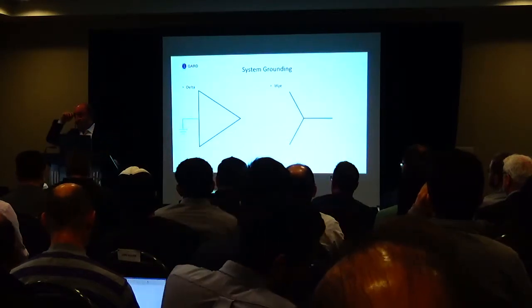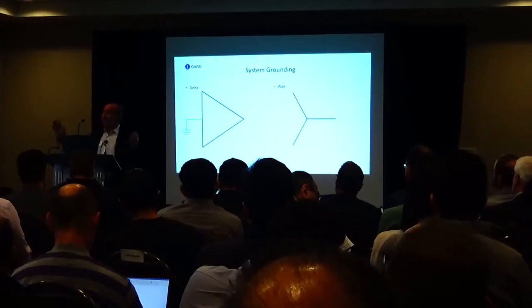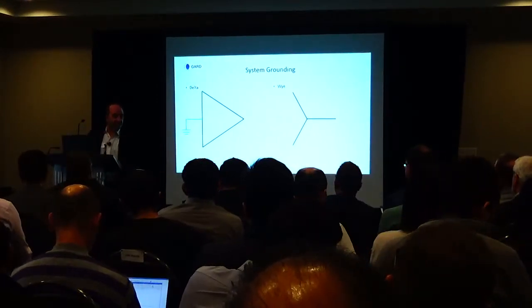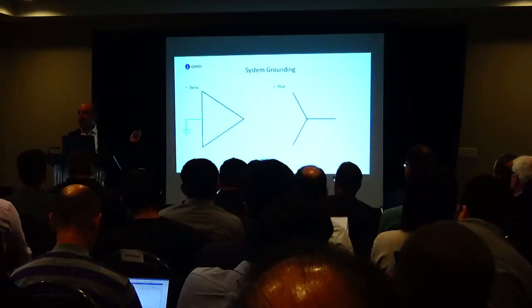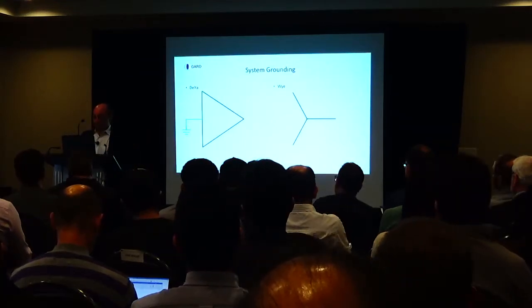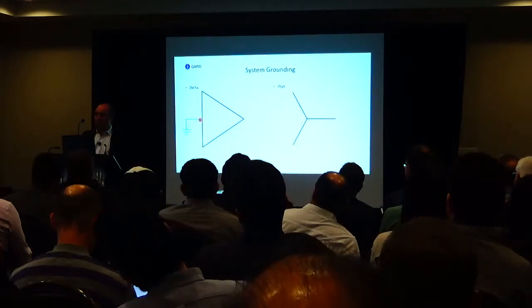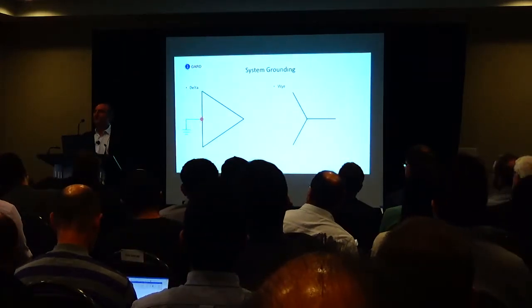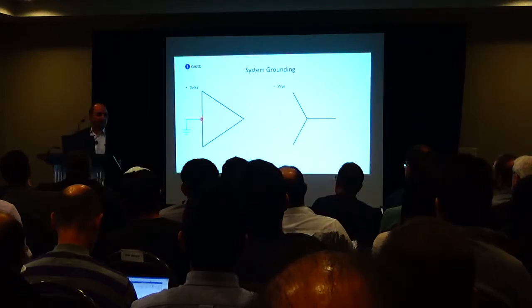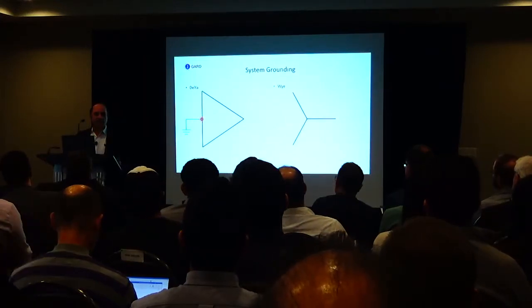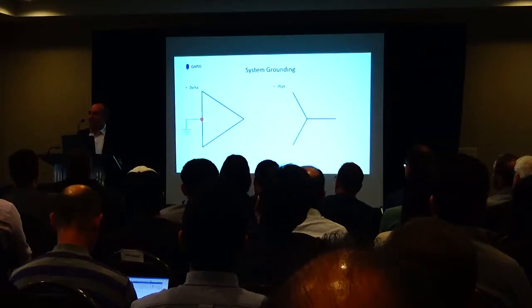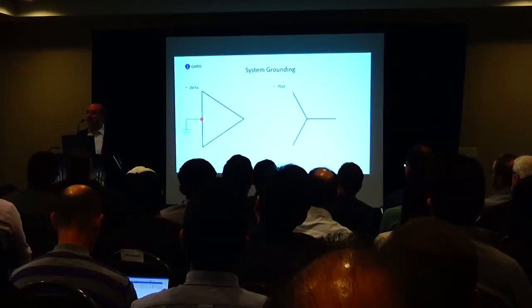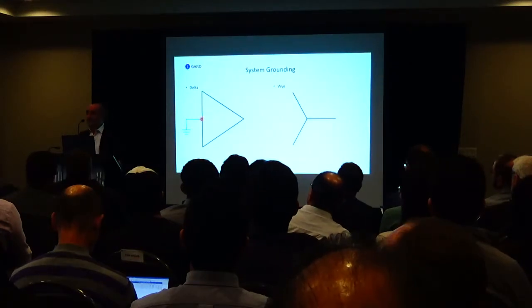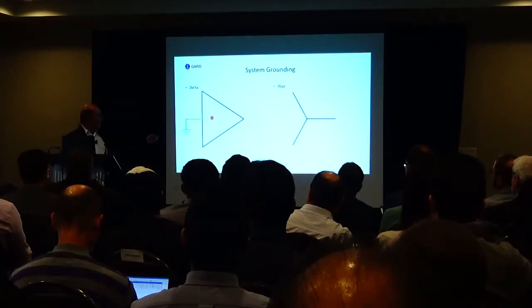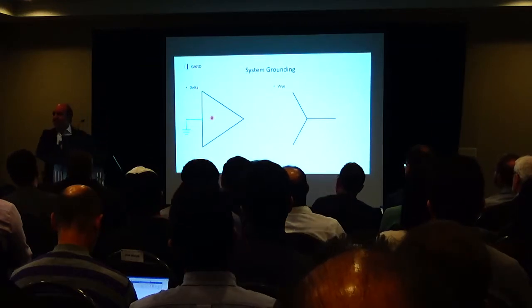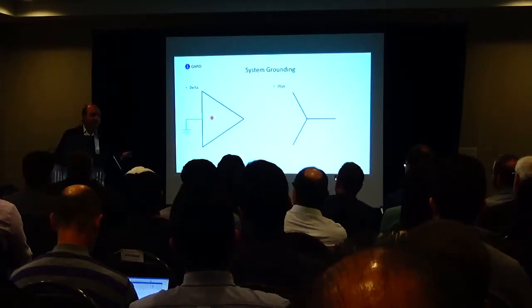So this is the one that you're used to. So you measure on, let's say for example, a 240 volt system. 240 volts phase to phase, that's what we're going to measure here. 120 volts from here to ground, and from here to ground. For sake of argument, let's call this the neutral, because you can make the neutral anywhere you want. How many different voltages can you get out of this system? It depends where you tap it along the... Well, there's the ground right there. Come on, I'm not trying to hide anything. 3 voltages, what are they?